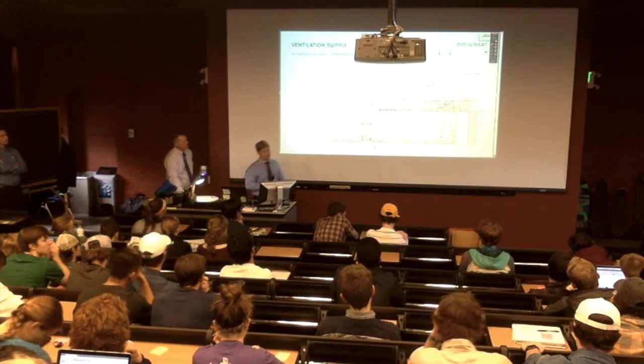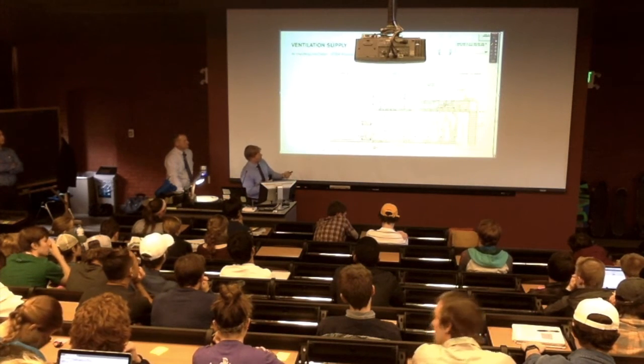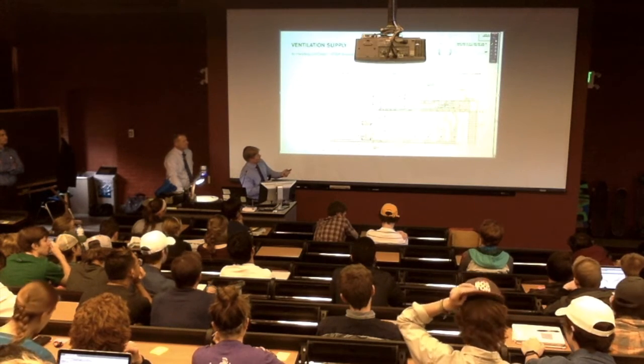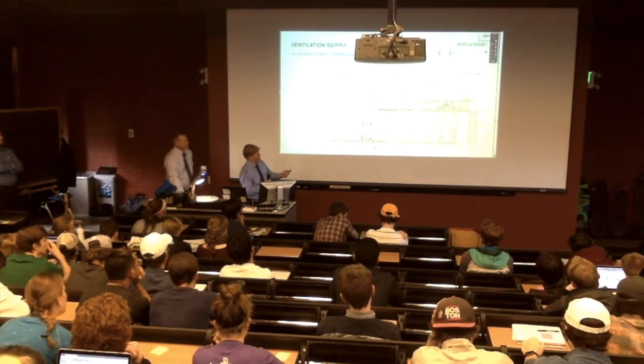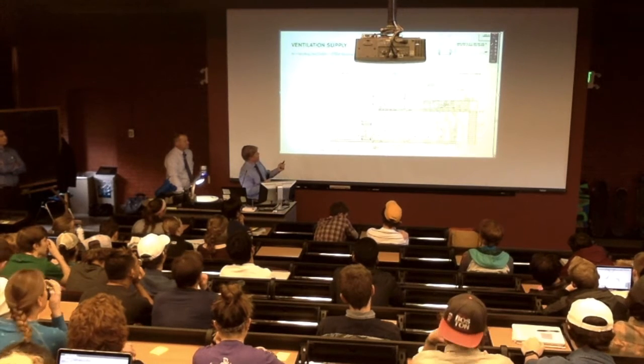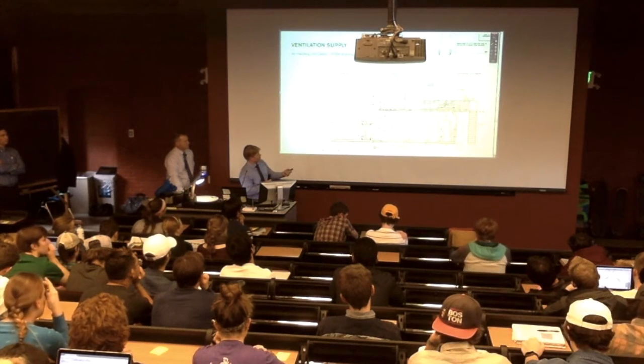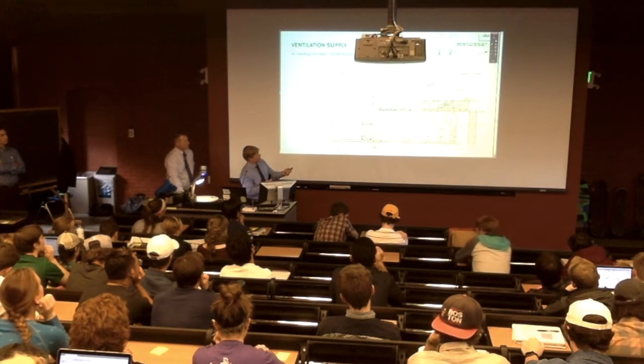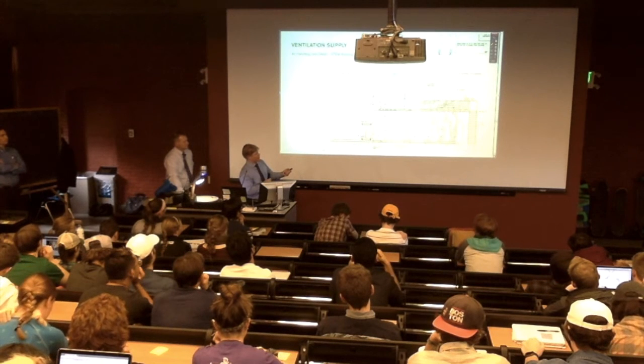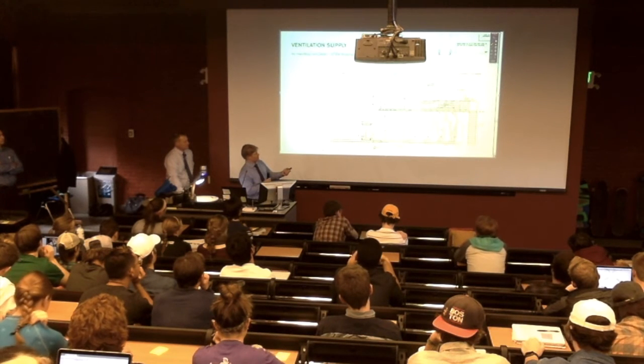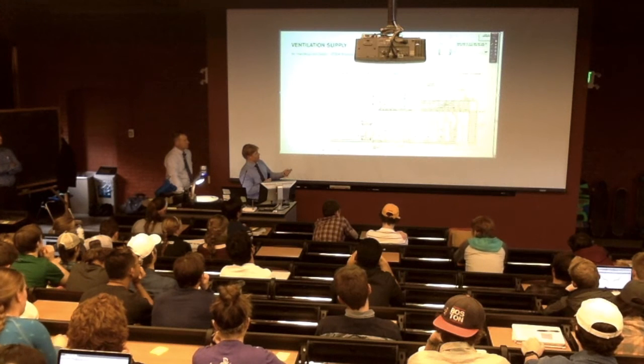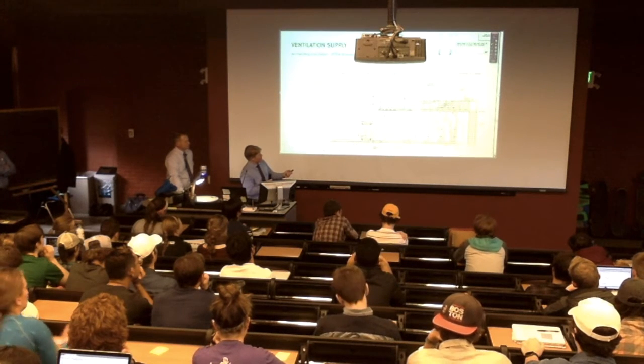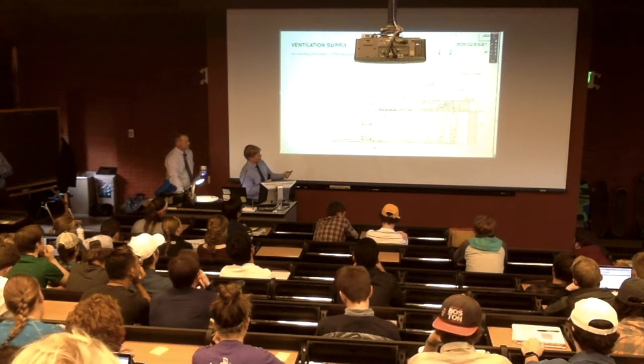So the heat recovery coil, that's the one where it actually has a paired set of coils up here. So this is where you pump glycol from the hot exhaust air. Exhaust air comes from the building, goes through the exhaust unit, up the stack, but it goes at 75 degrees. So when it's minus 20 outside, like it gets to be up here, you take 75-degree air and use that to heat up a loop of glycol.